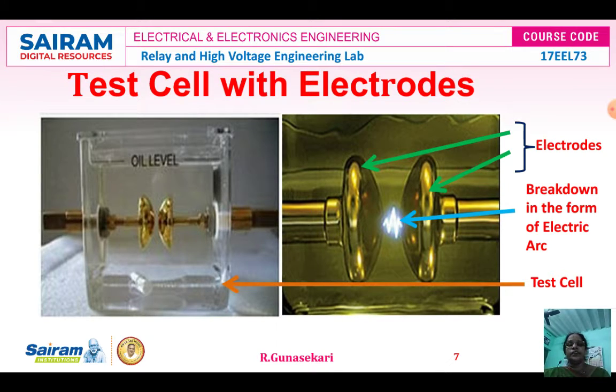The left hand side figure shows two sphere shaped electrodes. This is the test cell made up of glass. The oil level indicator is there. The second figure shows two electrodes. In between the electrodes, breakdown occurs in the form of electric arc, which is shown in the figure.